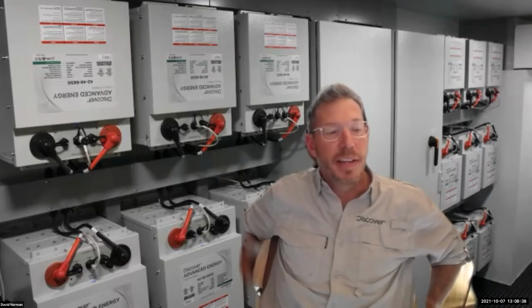Now, I've worked with Eric Wilson pretty extensively in the past and asked a lot of questions. For those of you who don't know, Eric is our battery head of engineering. And the way he explained it to me is the voltage is only used when you first power up the battery to just approximate what the battery's state of charge is, but it then goes into an active algorithm to determine the true state of charge after you get some power flowing.